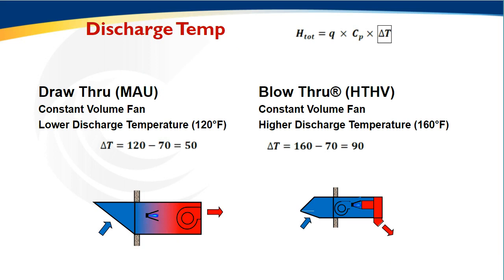So think back to our previous example of 10,000 CFM, heat to 70 degrees. If I'm trying to counteract the skin loss, really it's only that usable heat above my space temperature that I can use to heat any of those skin losses. And in this case, the HTHV has 90 degrees of temperature rise above space temperature versus the 50 degrees of the draw-through systems. That's an 80% difference in net BTUs delivered per CFM.